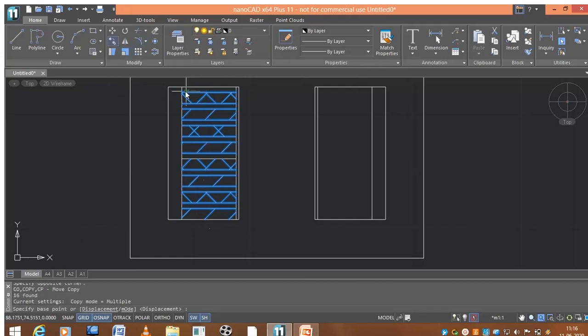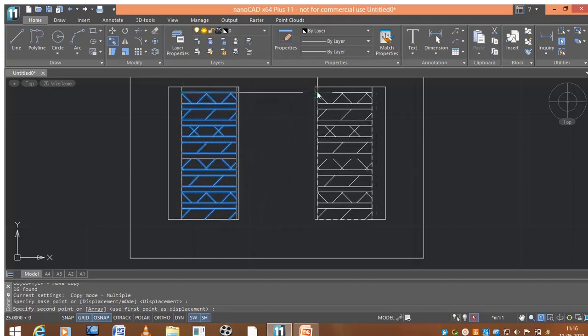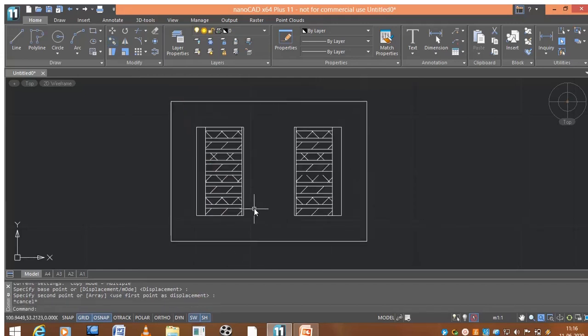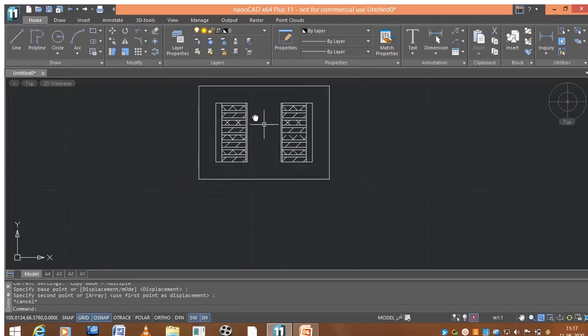I copy and paste the winding from one side to the other using the shift key to move it horizontally. This gives us four LV and four HV windings alternatively placed — and this is the sectional elevation of the shell type transformer.